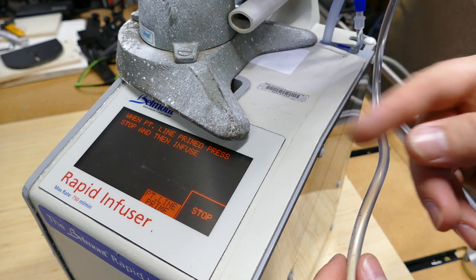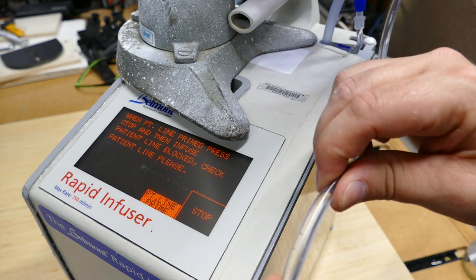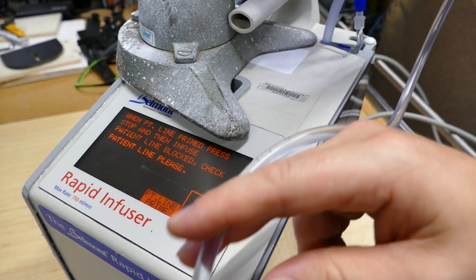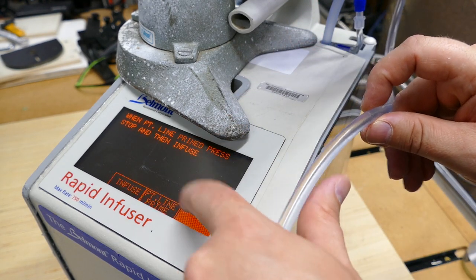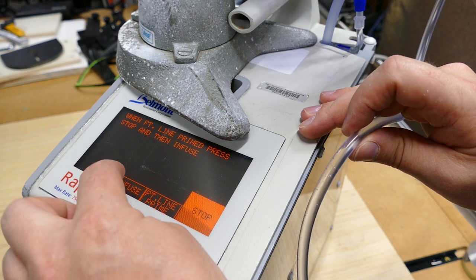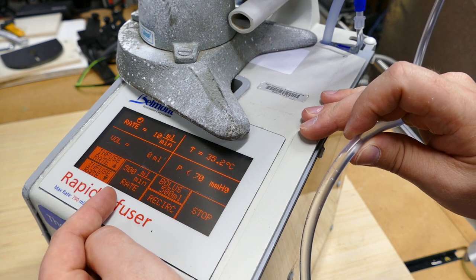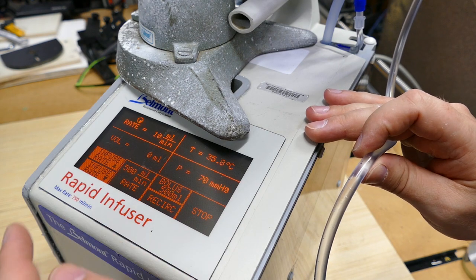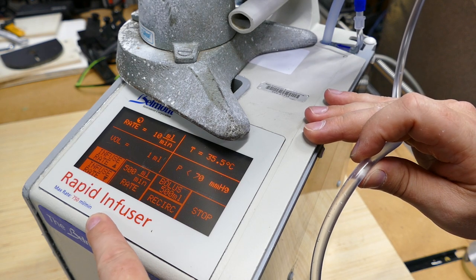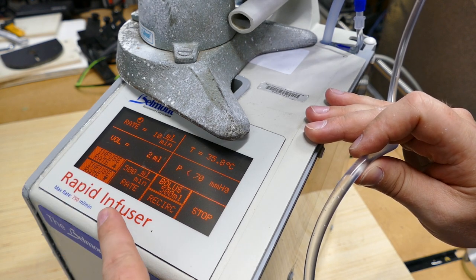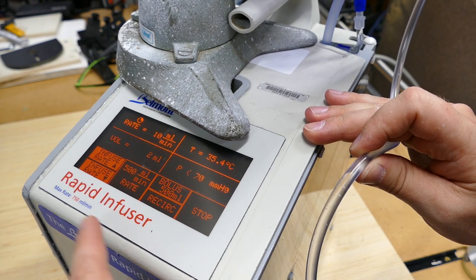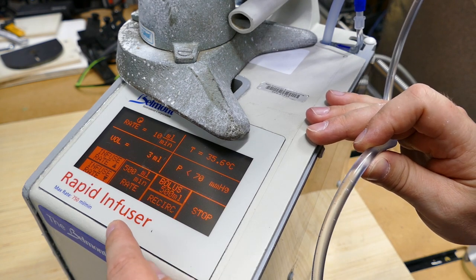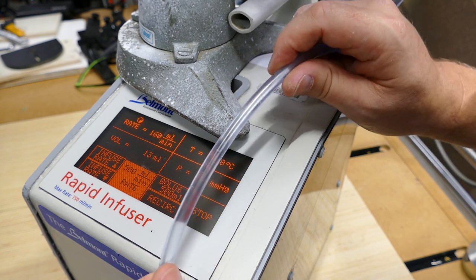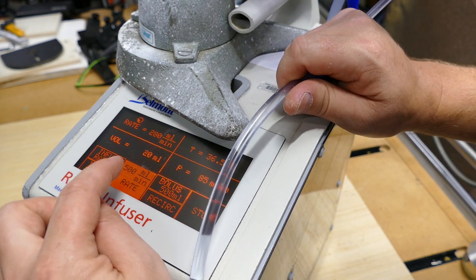You can probably hear it. The pump is barely spinning back there. It's just enough to get the air out of this patient line. And then we press stop. Now we're ready to infuse. The default rate is 500 milliliters per minute, a half a liter per minute. That's actually kicking as it is, but these units can either go up to 750 milliliters per minute, as you see here written right on the faceplate, or they go all the way up to 1,000 milliliters per minute, and that is just squeezing the fluid through. So what you do is when you are ready to go, you hit infuse, which is this button right here.